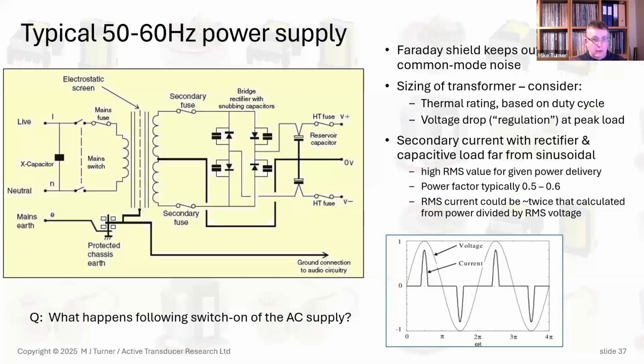And another gotcha in these is that because we're charging capacitors up every cycle with little pulses of current, the rectifier diodes only conduct at the peak of the incoming AC. So we get waveforms on the secondary and on the primary that look like this. And those are very far from sine waves. They've got a much higher root mean square ohmic heating value relative to the amount of power that they deliver. The power factor, if you like, of those windings is about 0.5 or 0.6 typically. And it means that if you want 100 watts out of the DC side of the power supply, you're probably going to have to size the transformer for something like 200 VA in order to do that continuously. And that's because of this rather nasty peaky waveform.